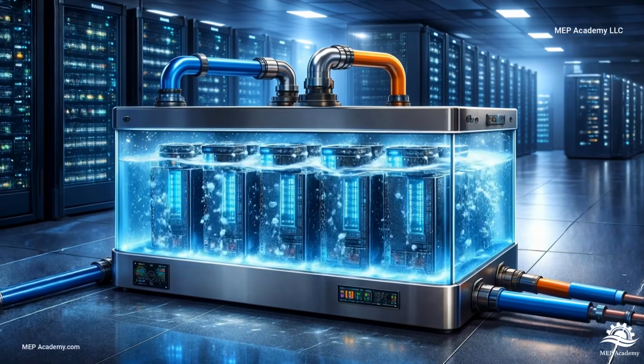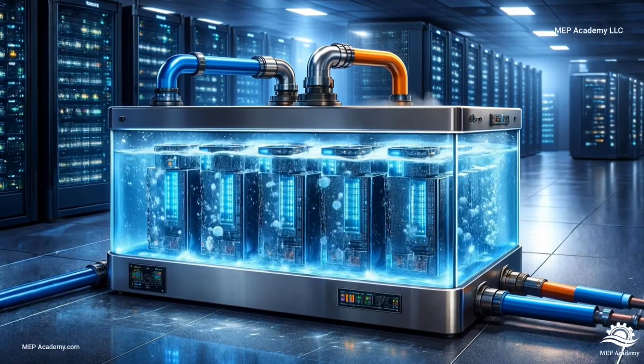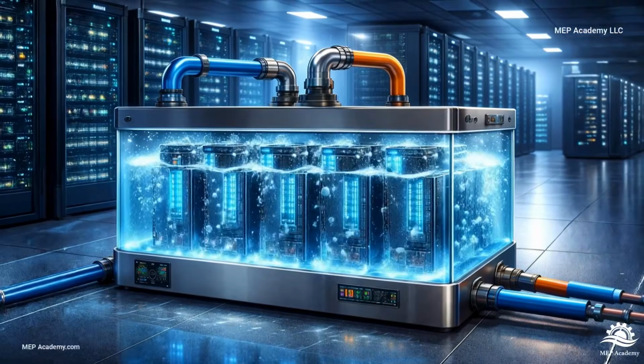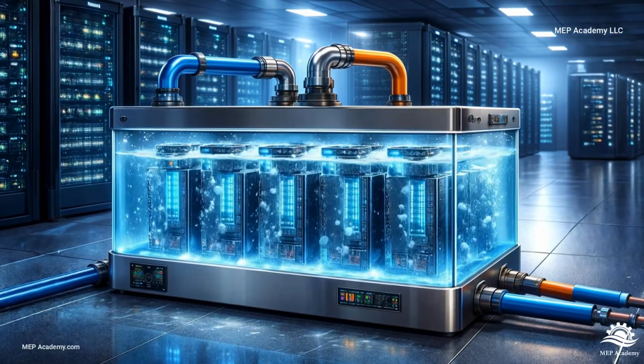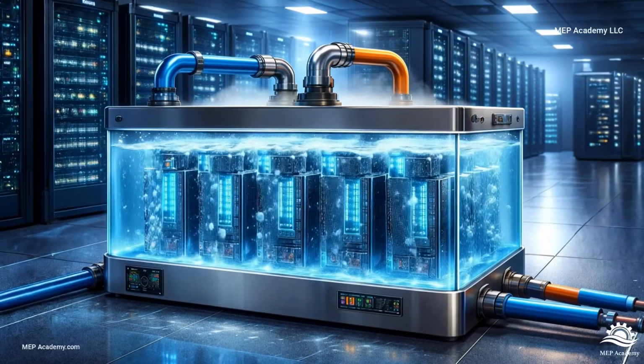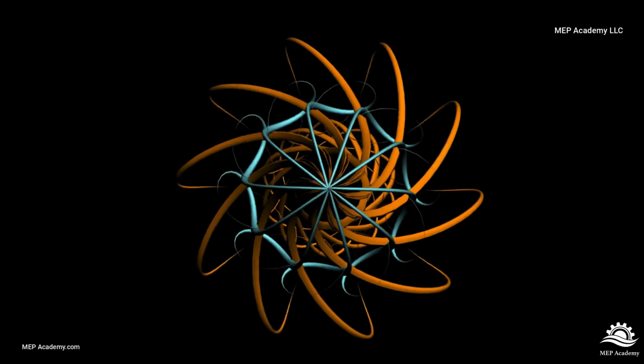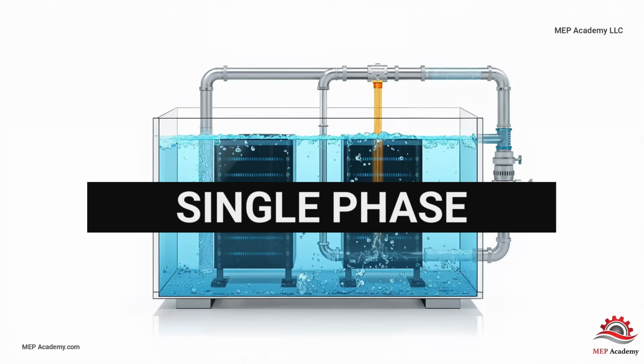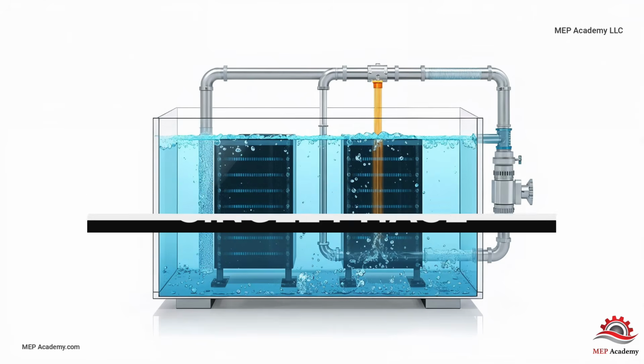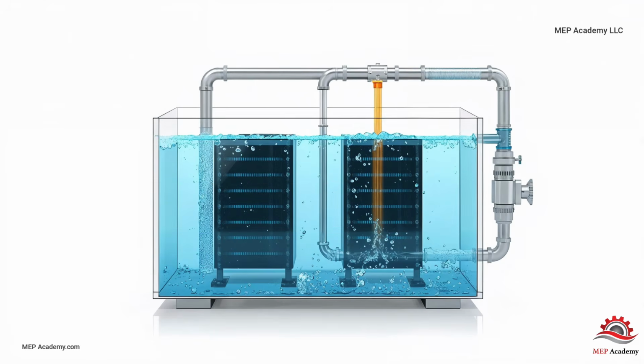As the servers generate heat, the surrounding fluid absorbs it directly. The warmed fluid then transfers heat to a cooling system. There are two primary immersion cooling methods: single-phase immersion cooling and two-phase immersion cooling. In a single-phase system, the fluid remains liquid throughout the process. Heat is absorbed and carried away through circulation.